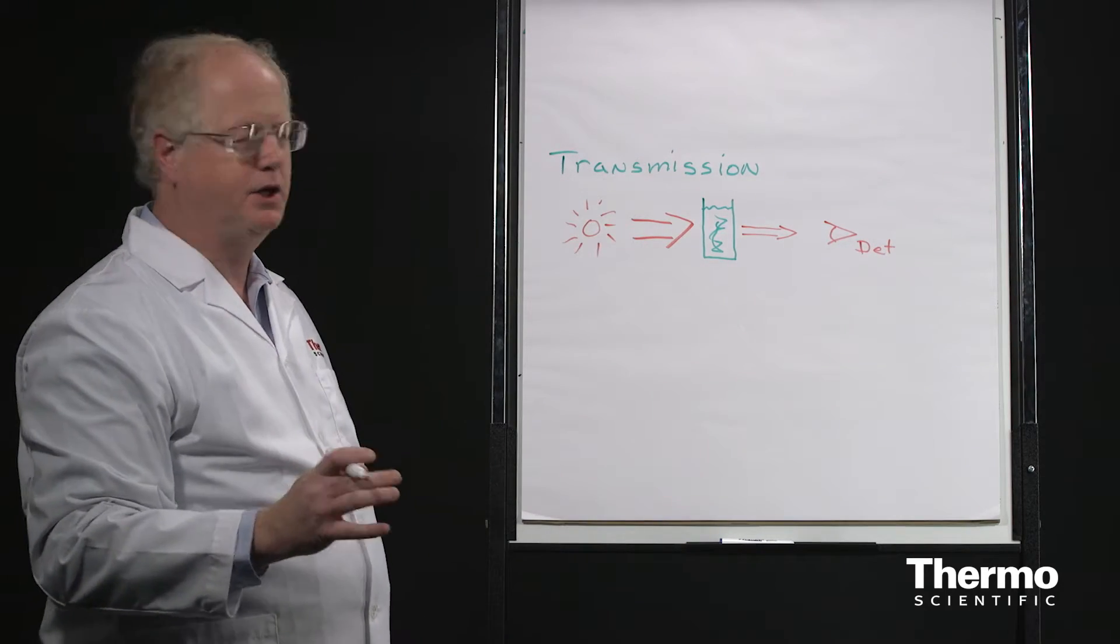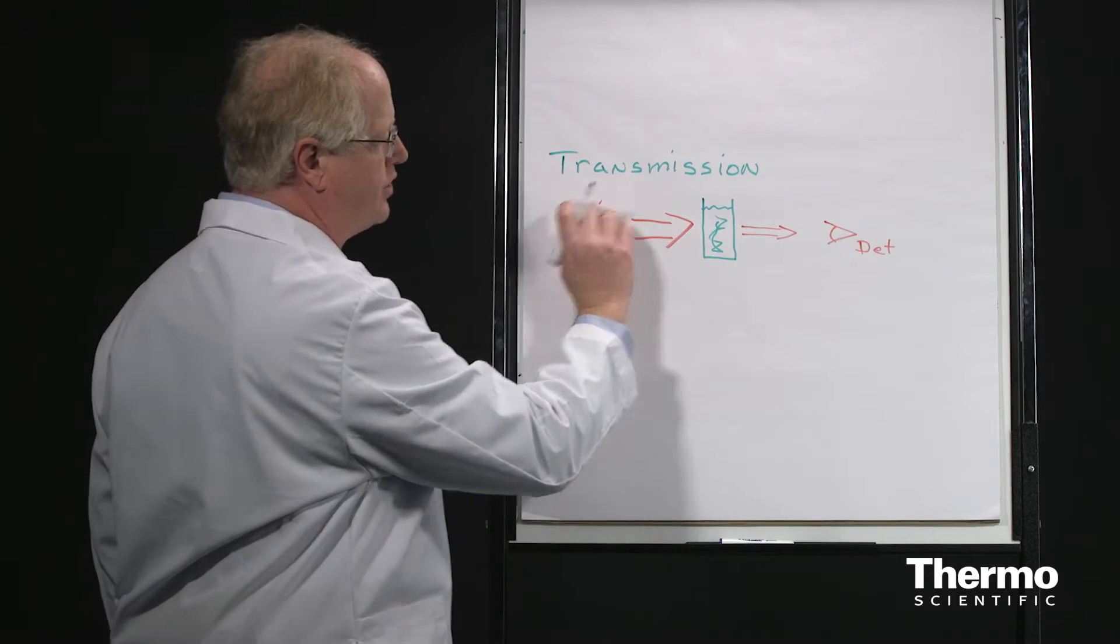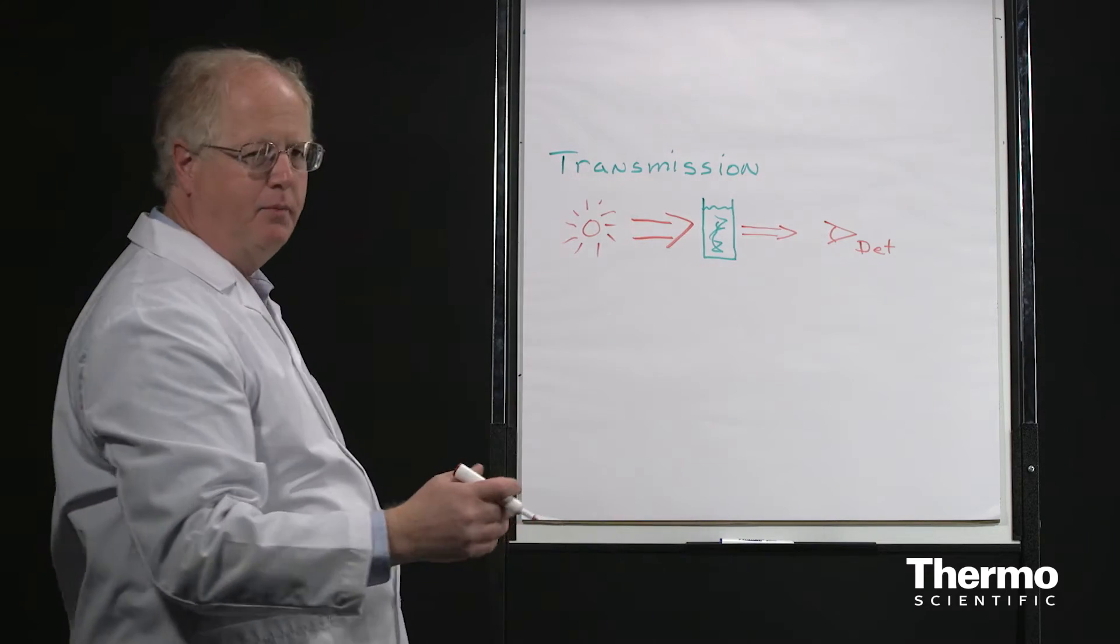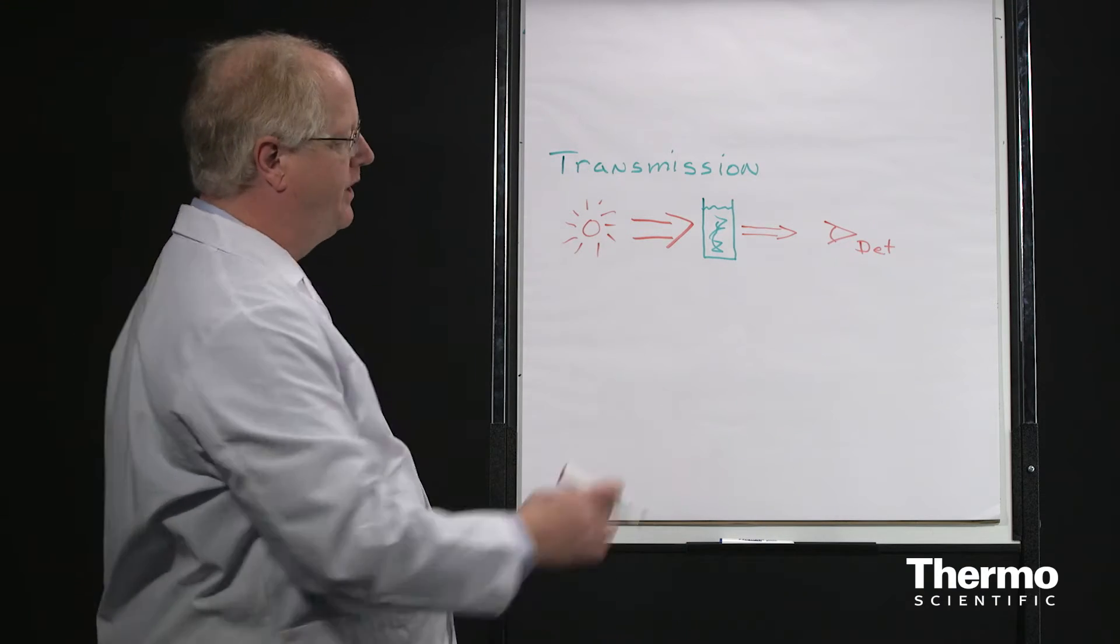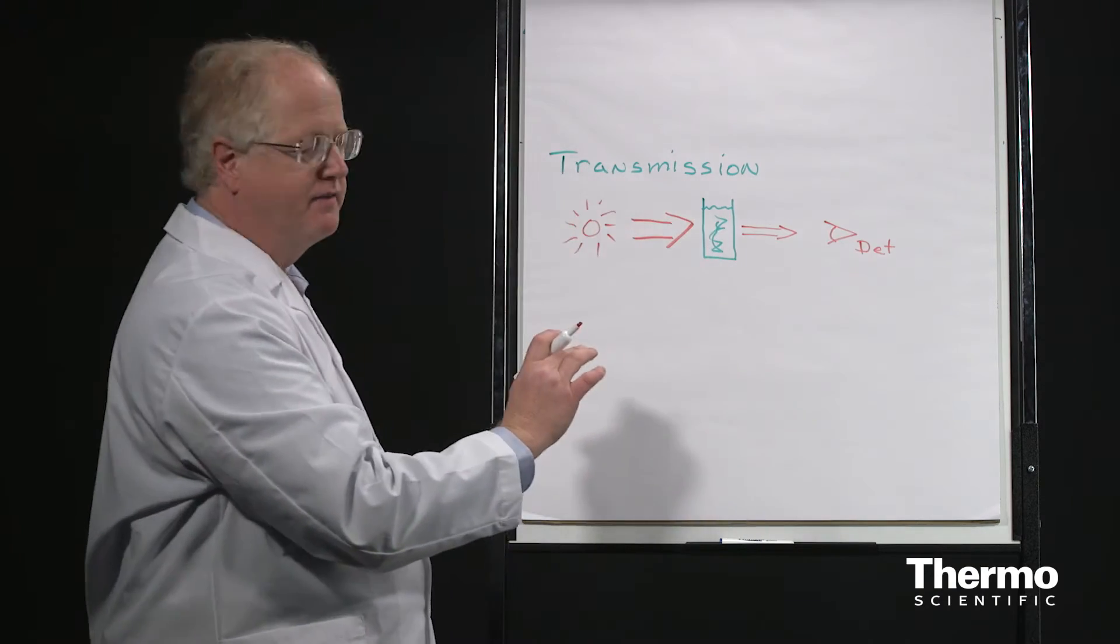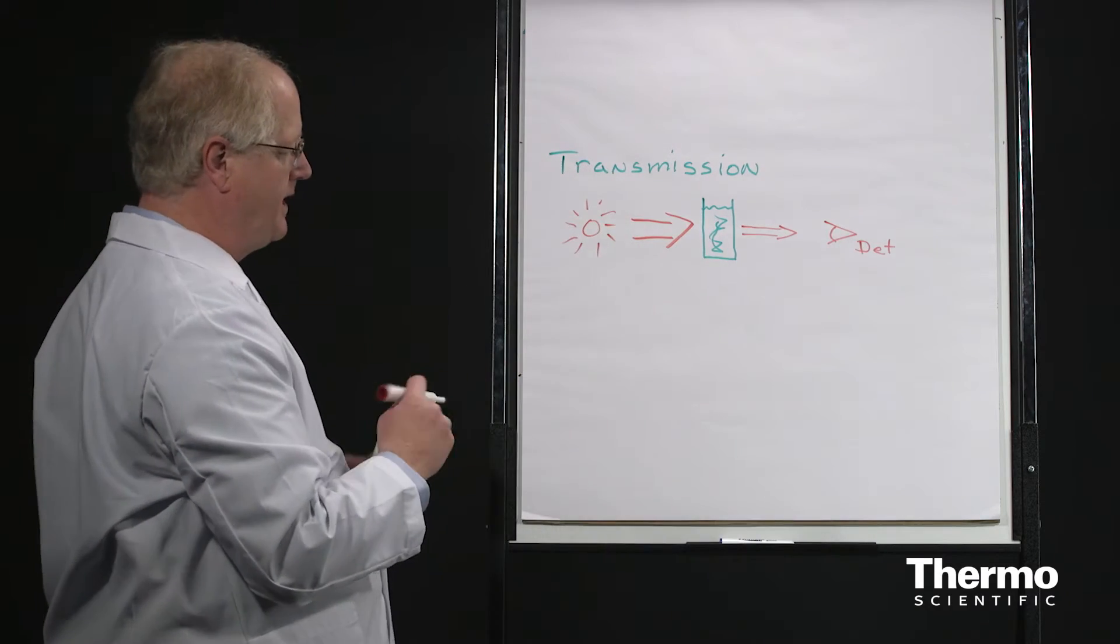That's all there really is to it. You have a sample in the beam between the source and the detector. The sample absorbs that light. We see that change. We take a spectrum without the sample present to give us a background, put the sample in, and look at the difference. That tells us how much light is absorbed.